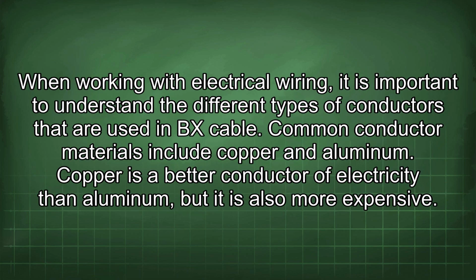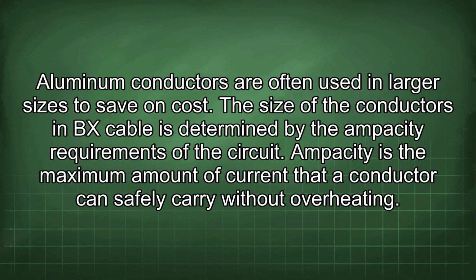When working with electrical wiring, it is important to understand the different types of conductors that are used in BX cable. Common conductor materials include copper and aluminum. Copper is a better conductor of electricity than aluminum, but it is also more expensive. Aluminum conductors are often used in larger sizes to save on cost. The size of the conductors in BX cable is determined by the ampacity requirements of the circuit. Ampacity is the maximum amount of current that a conductor can safely carry without overheating.